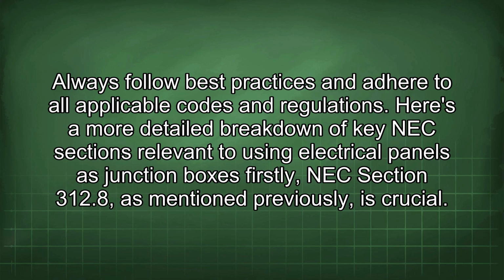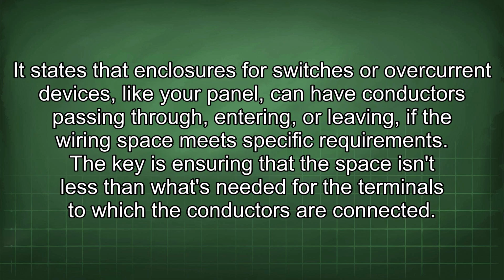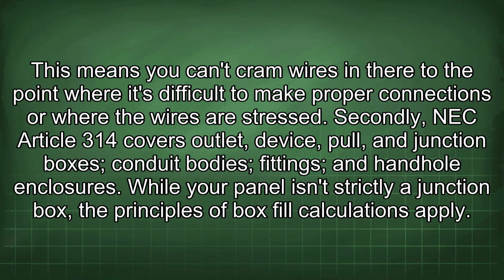Firstly, NEC Section 312.8, as mentioned previously, is crucial. It states that enclosures for switches or overcurrent devices, like your panel, can have conductors passing through, entering, or leaving, if the wiring space meets specific requirements. The key is ensuring that the space isn't less than what's needed for the terminals to which the conductors are connected. This means you can't cram wires in there to the point where it's difficult to make proper connections or where the wires are stressed.